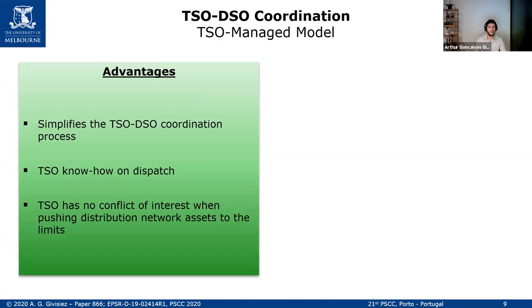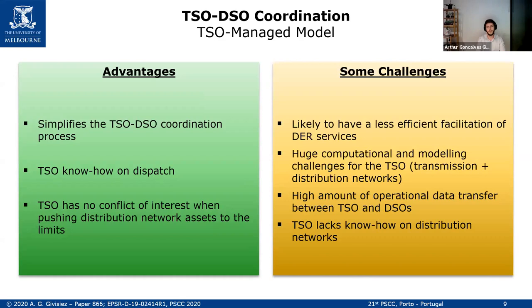There are some advantages to this model. It simplifies the TSO-DSO coordination, and the TSO already has know-how on this — they only need to expand it to the distribution side. The TSO also has no conflict of interest when pushing distribution network assets to their limits, since they don't own those assets. Challenges include less efficient facilitation of DER services because the TSO decides dispatch while the DSO controls voltages and transformer OLTC taps. There is also a huge computation and modeling challenge, a high amount of operational data transfer, and the TSO lacks know-how on distribution networks.